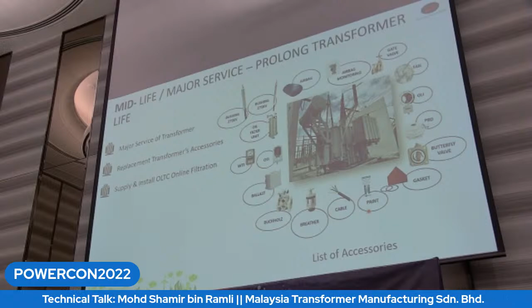And in terms of accessories, from our study on these transformers, no doubt the active part can last 30-40 years, but what fails earlier would be the accessories. Once the accessories fail, it also will bring down the transformer as well. That will impact the reliability of the transformer operation. So instead of spending on building more transformers, what we do is just replace the accessories. This is based on our years of study on the data collection.